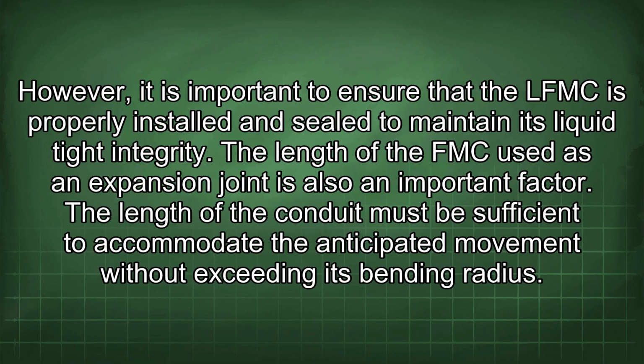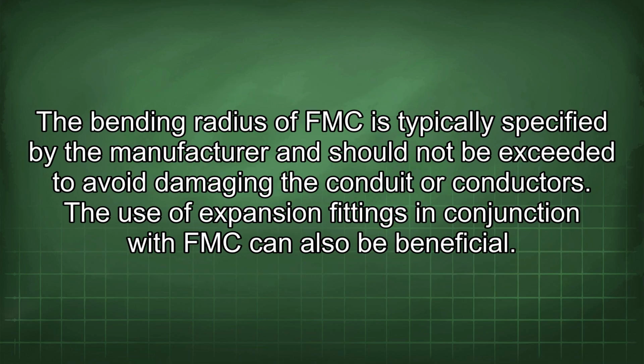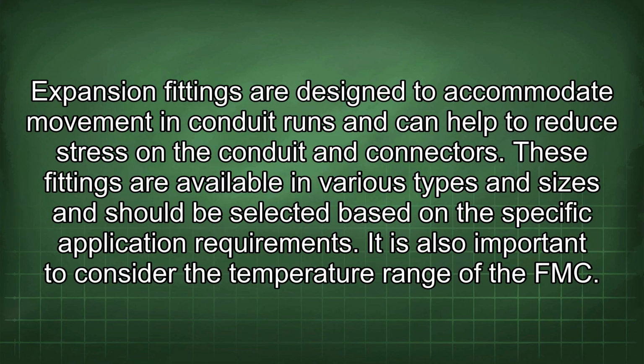The length of the FMC used as an expansion joint is also an important factor. The length of the conduit must be sufficient to accommodate the anticipated movement without exceeding its bending radius. The bending radius of FMC is typically specified by the manufacturer and should not be exceeded to avoid damaging the conduit or conductors. The use of expansion fittings in conjunction with FMC can also be beneficial. Expansion fittings are designed to accommodate movement in conduit runs and can help to reduce stress on the conduit and connectors. These fittings are available in various types and sizes and should be selected based on the specific application requirements.